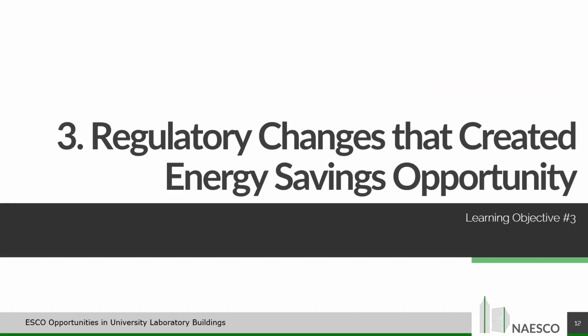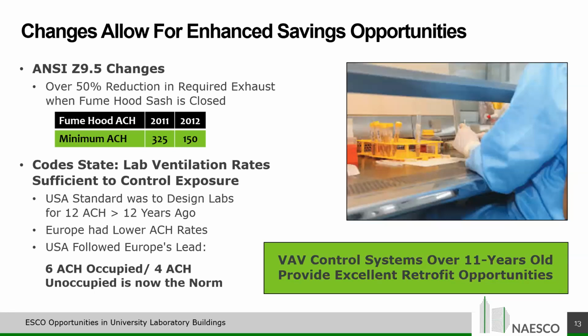So now let's talk about some of the changes that have happened in the code and the design practices over the years that have created more opportunity to do energy efficient retrofits in the lab space. ANSI Z9.5, as I mentioned before, is probably the key code, or the biggest code out there most people follow. And back in 2011, the closed sash ventilation rate was 325 air changes per hour. But in 2012, they changed it to 150 air changes per hour, meaning that you could reduce the amount of exhaust on your fume hood when the sash is closed by over 50%.